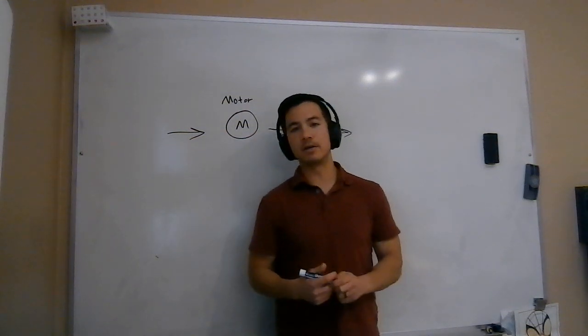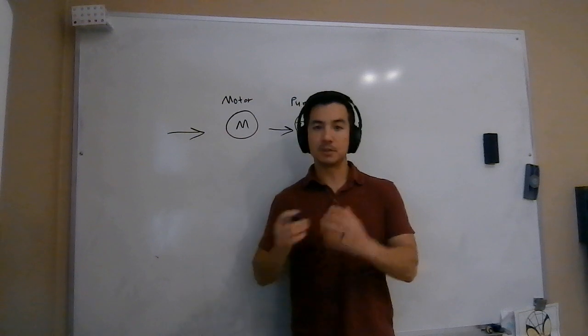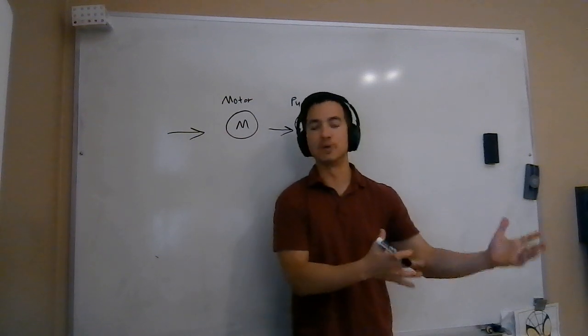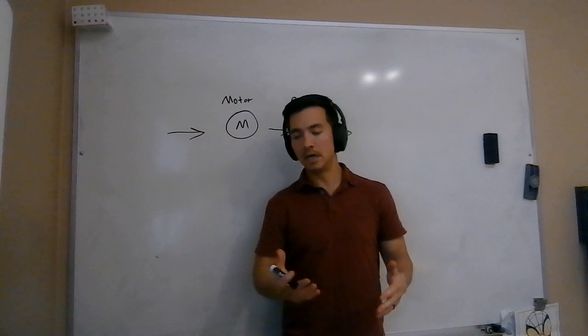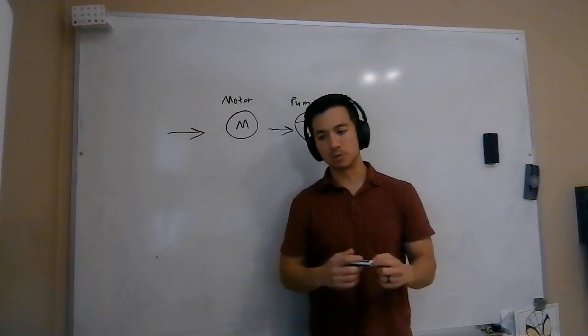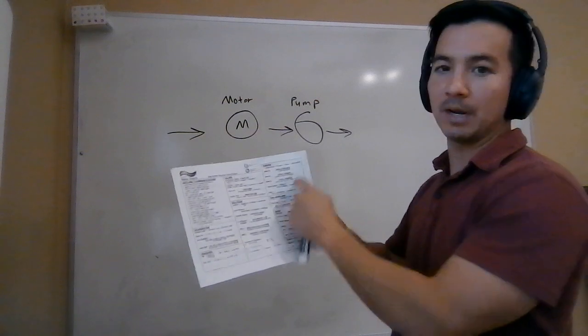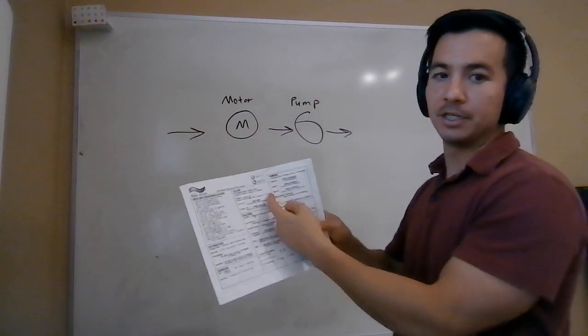In this video, we are going to be calculating horsepower requirements in order to pump a certain amount of water to a certain location. We're going to look at the parameters associated with that, and we're going to look at the three different types of horsepower that we calculate. The formulas come from the front page of your water distribution or water treatment conversion sheet, top right-hand corner. You're going to see pumping and three equations: water horsepower, brake horsepower, and motor horsepower.